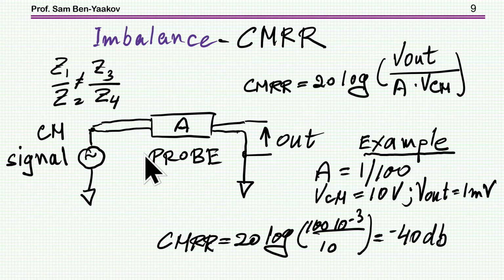For example, if we have a probe with a transfer ratio of 1 to 100 — an attenuation of 100 — and the common mode voltage is 10 volts, and we see 1 millivolt at the output, then the common mode rejection is minus 40 dB. This isn't considered very good, because if the voltage is 400 volts, we'd see 40 millivolts, which is quite a bit.